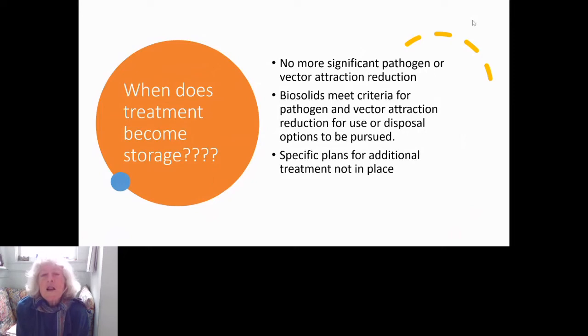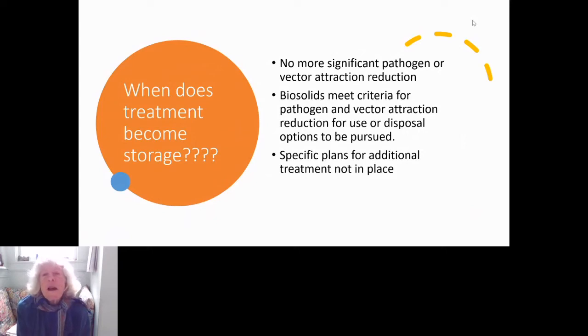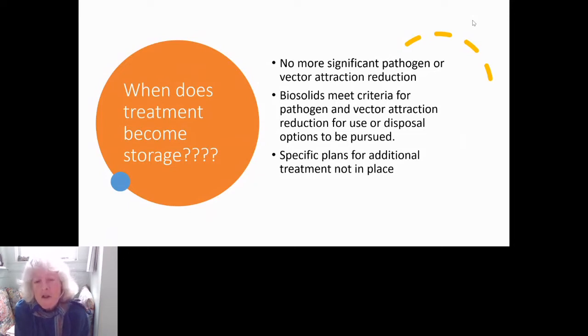If the sludge has reached the point where it meets the criteria for pathogen and vector attraction reduction — dried for more than three years and dried to over 90% solids — then we'd consider it storage as opposed to treatment. If there are specific plans to dry it further or other plans for it, that should be documented. Otherwise, at some point we'd say it's no longer being treated, it's storage, and if it's more than two years, it's surface disposal and you need to meet the surface disposal requirements.